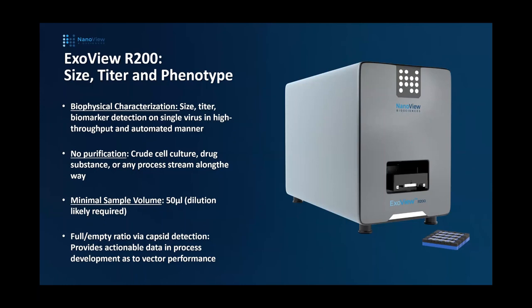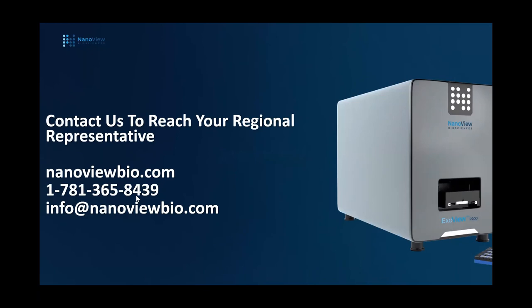Wrapping up: the ExoView R200 provides size, titer, and phenotype capability — biophysical characterization of single virus particles including size, counts, and biomarker detection — in a high-throughput automated system. No purification is required; crude cell culture, drug substances, any process stream along the way are welcome. Minimal sample volume — never more than 50 microliters, and often just a couple of microliters to get really nice data characterizing thousands of single virus particles from your mixture. This full/empty ratio via capsid detection provides actionable data for process development, vector performance, and tracking additional particles moving through separations. We will directly follow up with all poll requests. Contact us at info@nanovbio.com or reach your regional representative. Thank you for joining today.